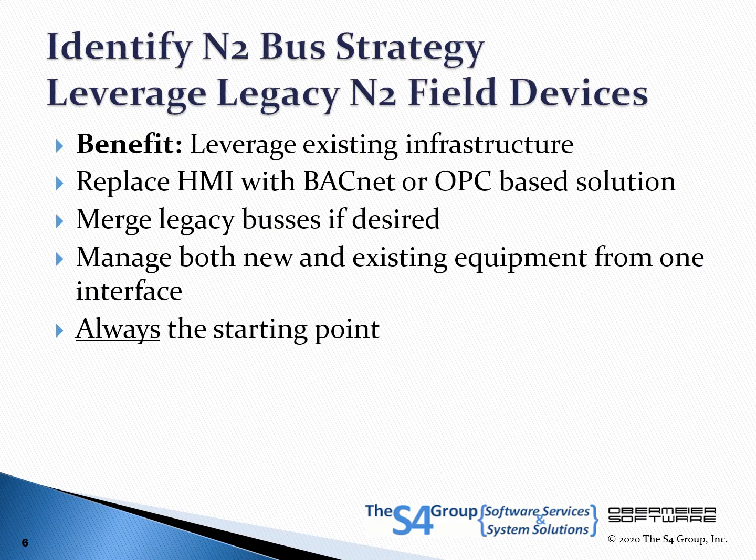The S4 Open Management Console contains a configure wizard that will discover all N2 Open, VMA, and System91 devices on the bus. Assign S4 device templates to all application-specific controllers. Identify vendor, Metasys integrator, and Centaurus integrator devices. Identify DX9100 systems. The S4 device templates are included for each Metasys hardware type and application.